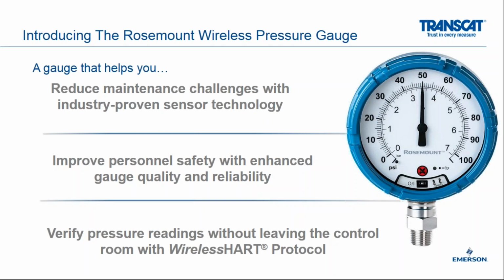So what this gauge is ultimately going to do, very high level, it's going to reduce those maintenance challenges. It's using an industry-proven sensor technology, different from a Bourdon tube technology. It can improve personnel safety. We're going to eliminate a lot of these hazards that you traditionally might put your workforce through when buying Bourdon tubes. And then you can also verify these readings. It's a smart gauge, so there's a lot more information than just where the needle's pointing that you can hopefully take some action on.